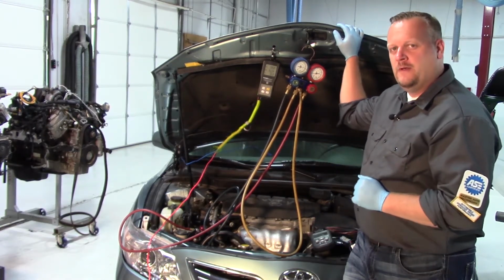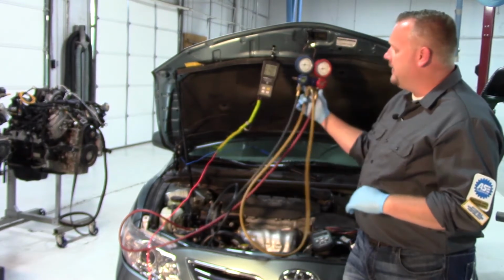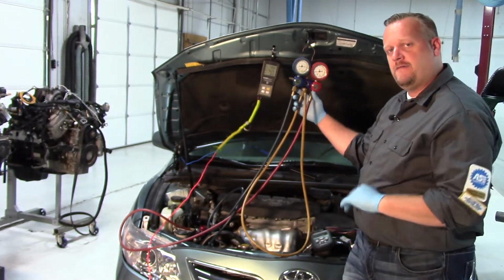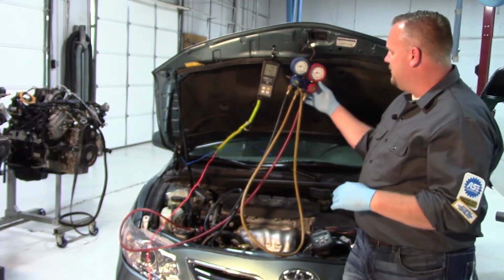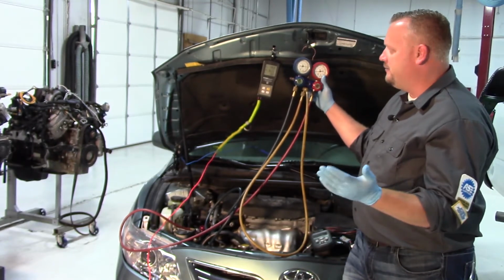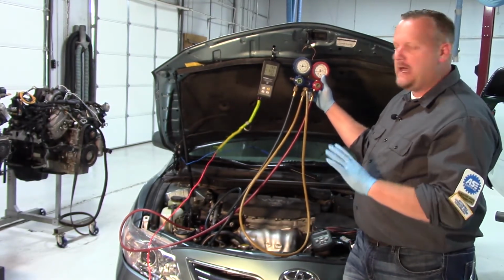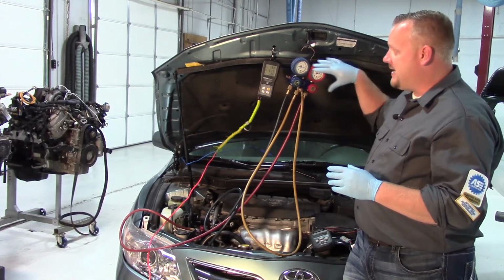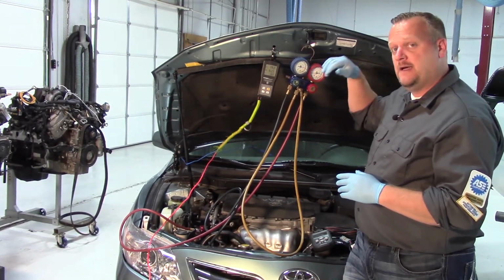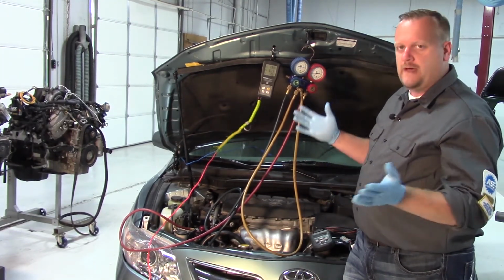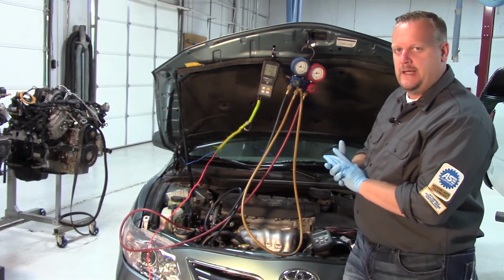That's not good, especially on a day when it's 110 degrees outside. Not real comfortable. So first thing we need to do is hook up our gauges and verify the charge level. We're in about an 80-degree shop, and we've got roughly 100 psi on the high and low sides of our gauges. We've got enough freon that this compressor should be engaging.